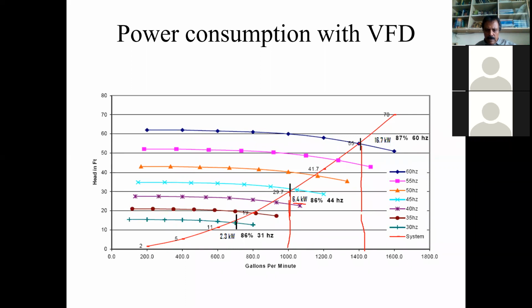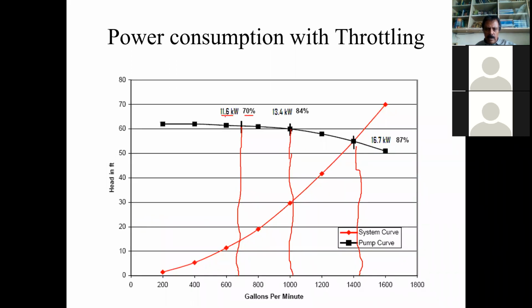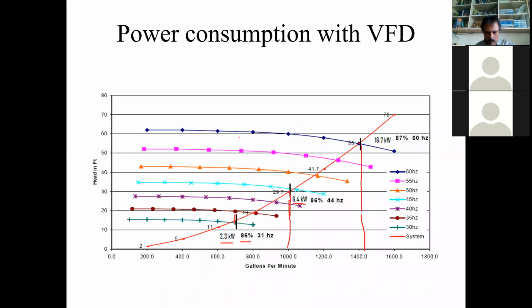When you reduce it to 700, somewhere here, the power keeps coming down further to 2.3 kilowatt. So 2.3 kilowatt at 700 GPM. You look at the efficiency, it still remains at 86%. No change in the efficiency. Whereas for the same 700 here, when you throttle, the power is 11.6. So 11.6 versus 2.3 here.